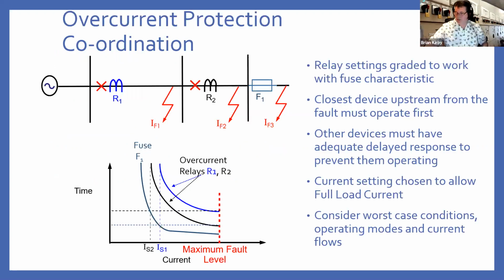So I mentioned earlier, I would come to that curve I showed you for the coordination of our protection. So if you look at this network here, we have a source on the left. I haven't shown any step-up transformers or anything, but assume that source is our distribution network, say, and we have several stages of feeder, and then our final stage is protected by a fuse. So we have 3 fault inception points. For simplicity, I'm assuming that regardless of where the fault happens, it has the same maximum fault level. And what we want to do is make sure that relay 1 only operates for this fault here, relay 2 for this fault, and fuse 1 for this fault.